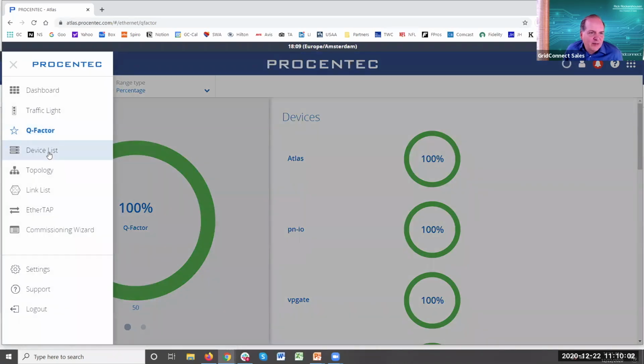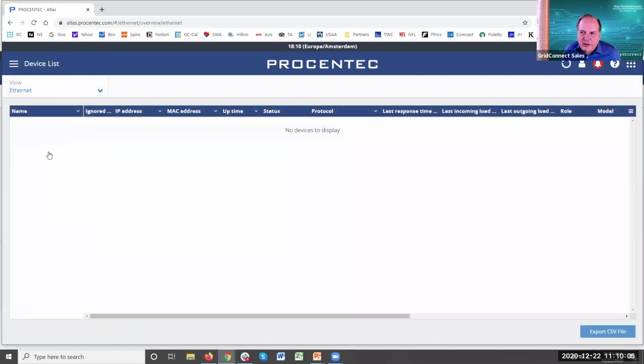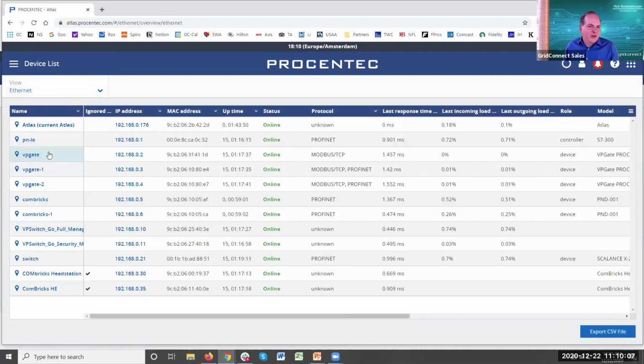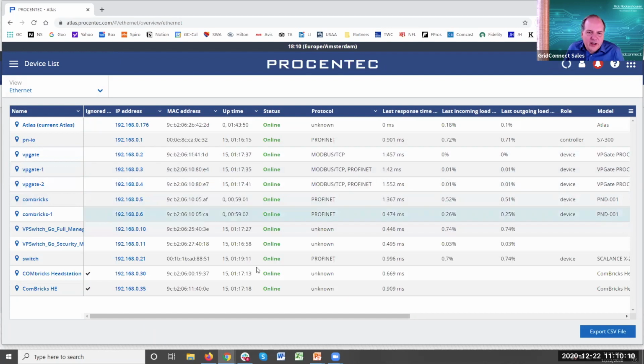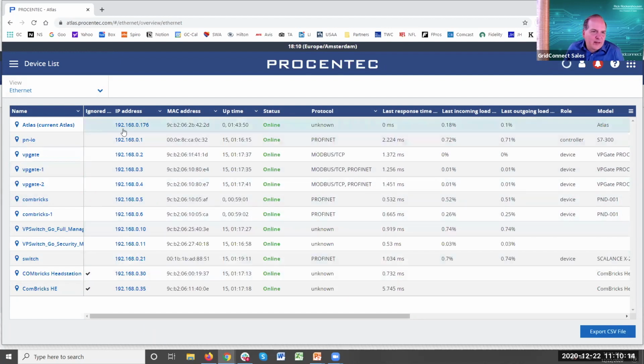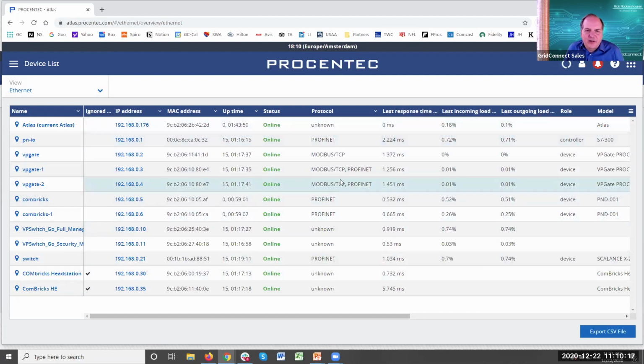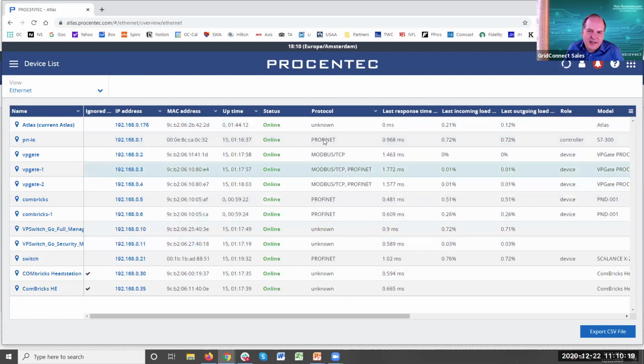All right, onto the device list. This is something I mentioned earlier and you saw a few screenshots during the PowerPoint presentation. So here's all my devices - you can see the protocols, the addresses, the IP and MAC addresses, how long they've been up, their current status, and what protocol they are working with: Profinet, Modbus TCP. The unknown ones tend to be managed switches, because managed switches aren't sending out Profinet or Ethernet IP packets on their own - they're just switching packets. And we also see the Combricks down here, which is interesting.